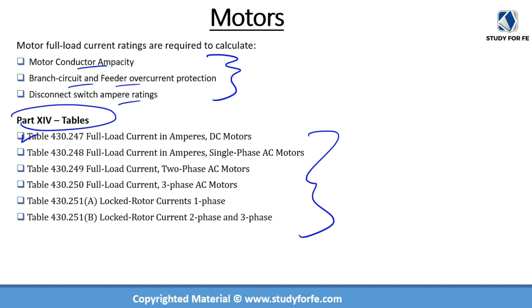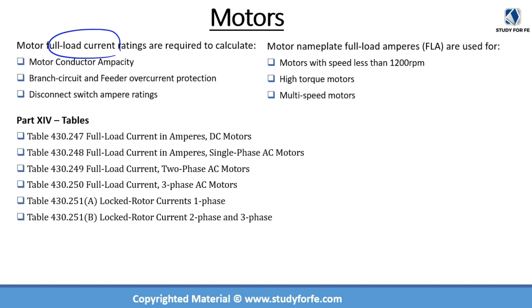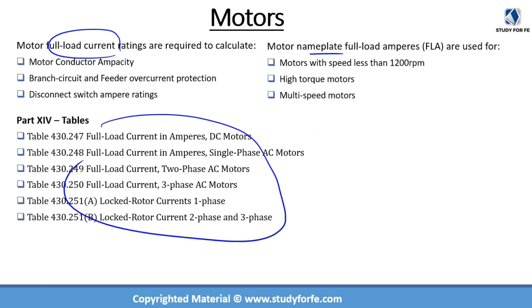Part XIV contains these important tables: Table 430.247 deals with FLC for DC motors; 430.248 deals with single-phase AC motors; 430.249 deals with two-phase AC motors; and probably the most important, 430.250, deals with three-phase AC motors, which are quite commonly used. There are some unique cases where we use the nameplate full-load amps instead — specifically for motors with RPMs less than 1200, high-torque motors, and multi-speed motors. But for all practical cases, your FLC will come from Part XIV tables, depending on the type of motor you're using.